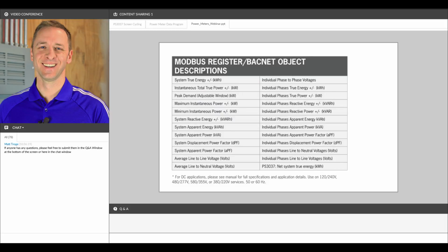Here's a list of the common Modbus register or BACnet object descriptions that show some of the most commonly used electrical parameters that these devices are going to measure. And they include system true energy, peak demand, and this can be measured on the total circuit or each individual phase of the circuit. You can get average line voltage, apparent power factor, and a number of others. There's several dozen different parameters that this device can measure. These are some of the most common.